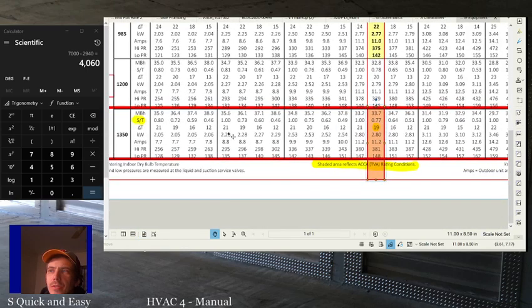So the numbers they give us right here are MBH. So this is thousands of BTUs. This is how many thousand BTUs this equipment puts out. All right, this is our S divided by T, so this is our sensible divided by total. And this is actually at 0.77 sensible heat ratio. So that means 77% of this 33,700 is sensible, and 23% of this is latent. So we'll do that math shortly.